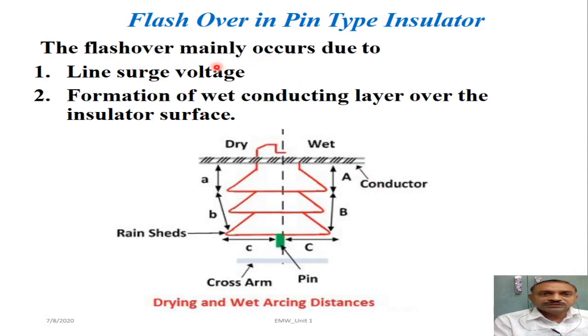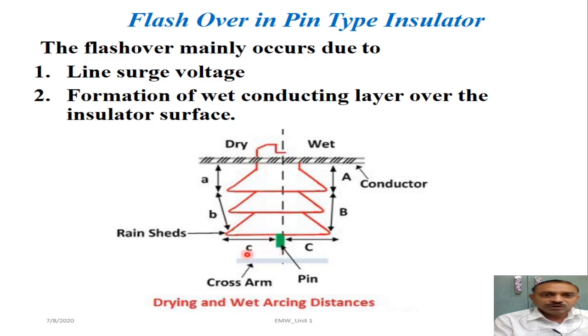Flashover can occur because of two reasons. One is the line surge voltage, and another is the formation of a wet conducting layer over the insulator surface. If a fault takes place somewhere in the power system network, a surge voltage may develop and flow through the conductor, causing the electric stress from the conductor to the pin or cross arm to increase sufficiently to produce a flashover.